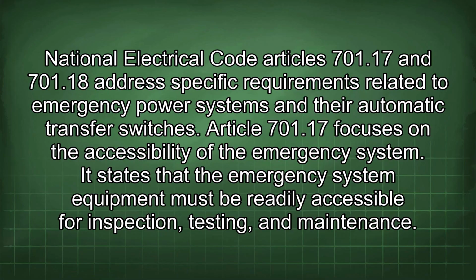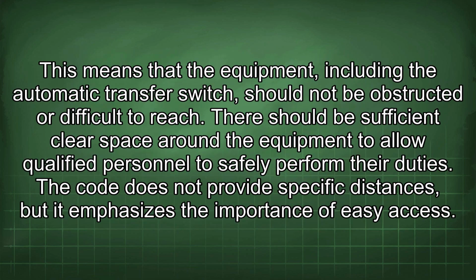National Electrical Code Articles 701.17 and 701.18 address specific requirements related to emergency power systems and their automatic transfer switches. Article 701.17 focuses on the accessibility of the emergency system. It states that the emergency system equipment must be readily accessible for inspection, testing, and maintenance. This means that the equipment, including the automatic transfer switch, should not be obstructed or difficult to reach. There should be sufficient clear space around the equipment to allow qualified personnel to safely perform their duties.